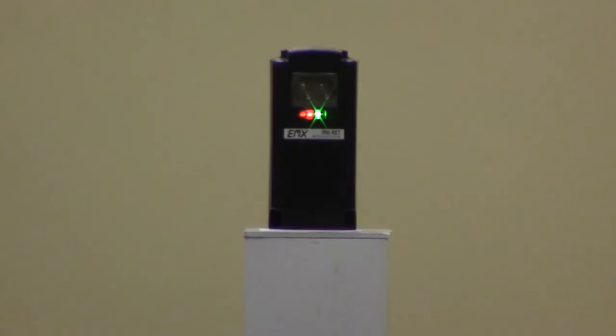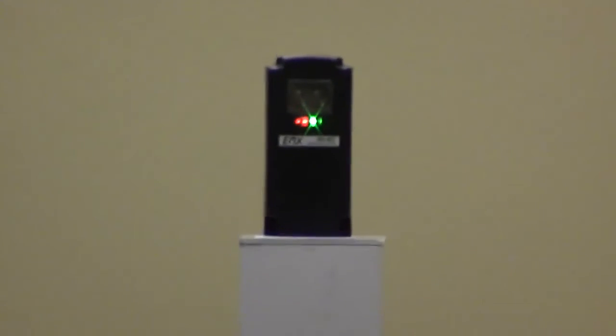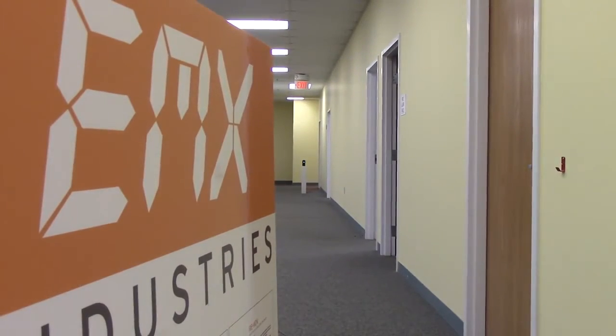This is a demonstration of the IRB-RET retroreflective photo-eye. We're going to measure the excess gain at the maximum rated distance of 60 feet. Excess gain is a measurement of light energy over and above the minimum amount required to operate the photo-eye. The extra light, the extra sensing energy, is used to overcome signal reduction caused by rain, fog, or snow.